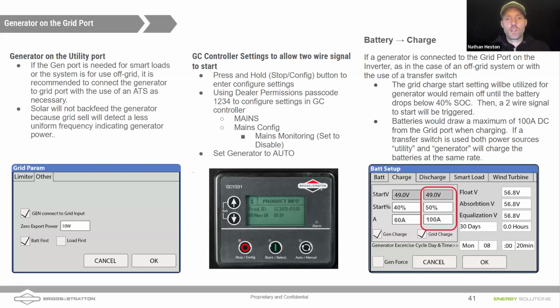We're including those instructions here again if you've got a Briggs and Stratton generator. Under the battery charging, now we're going to program the settings where we want the charge cycle to start on the column on the right. And we need to have the grid charge box checked because that's where the power is coming from. So before, when I mentioned those two columns, it's not really the device, but it's the location, the port where that power is coming from.